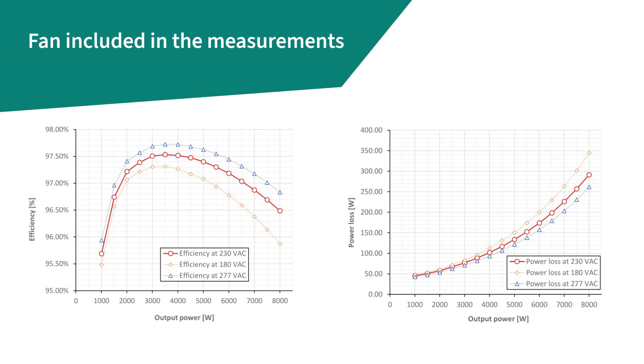For 230 volts AC, the efficiency is peaking to 97.5% at around 50% of the rated load and is 96.5% at full load. Losses are also reported in all three cases.